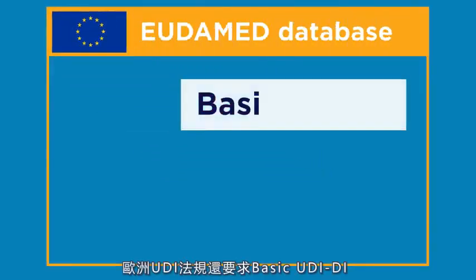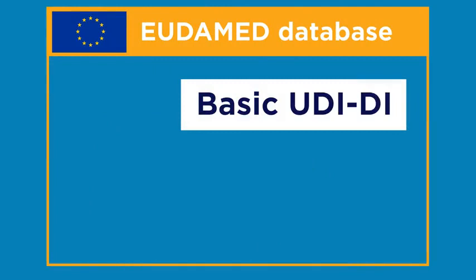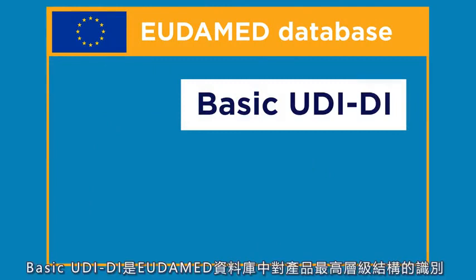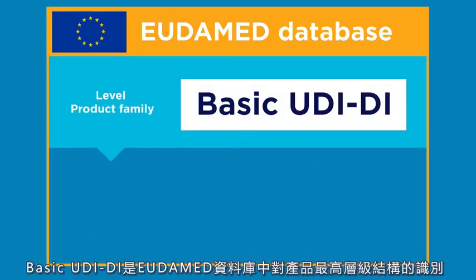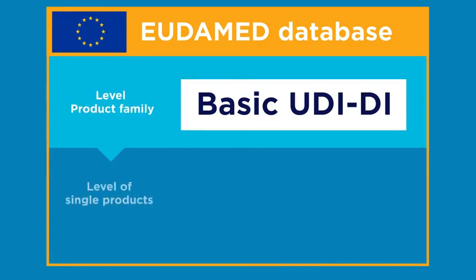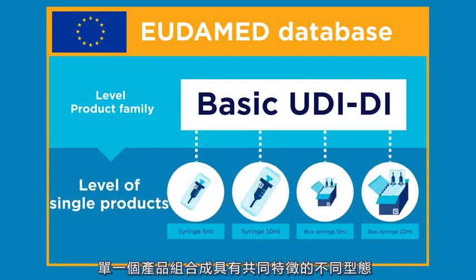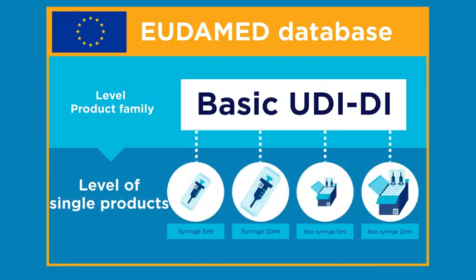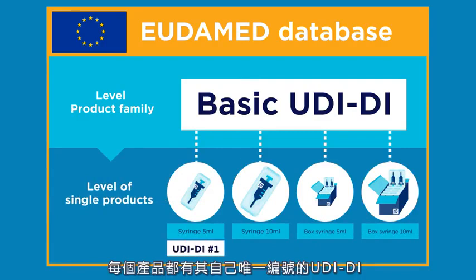The European UDI regulations also require a basic UDI-DI. The basic UDI-DI is the highest level of identification of the product hierarchy within the EUDAMED database, and identifies an entire product family or a product model. In a product family, individual products are combined in different variants and with common characteristics. Each product has its own unique number, the UDI-DI.